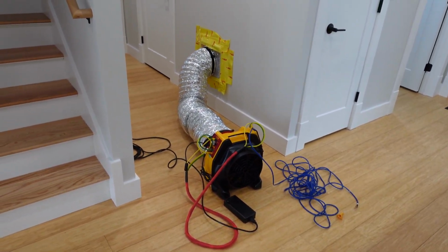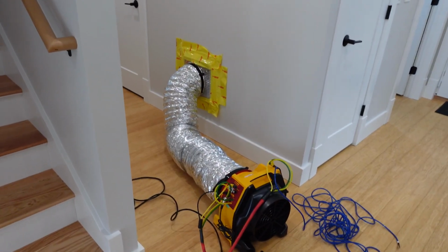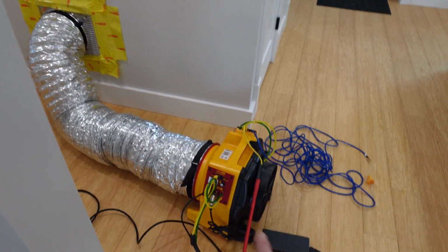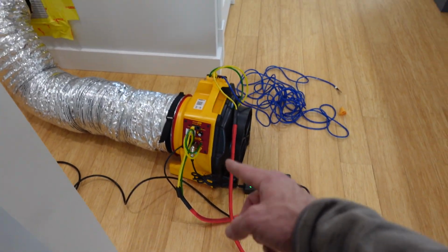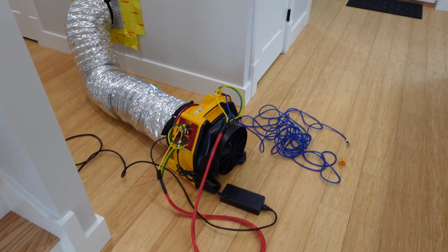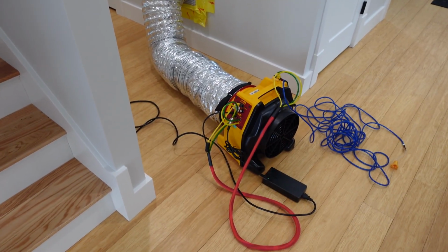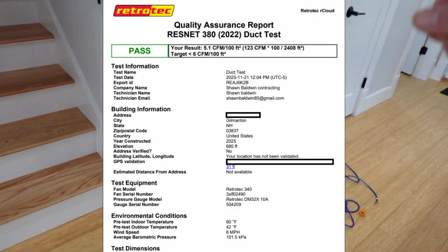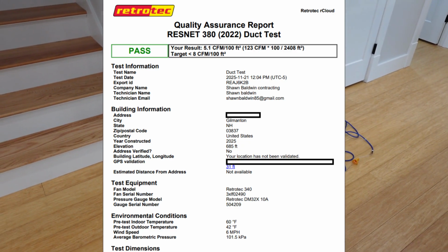Today I'm going to run two tests. First one is a duct leakage test, and the second one is a total system airflow test. Most people look at this device here and think this is just a leak detector, and it does really well at that. The first test we're going to do is a duct leakage test by hooking it up, sealing everything off, and measuring the airflow.